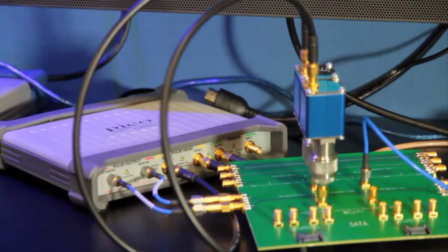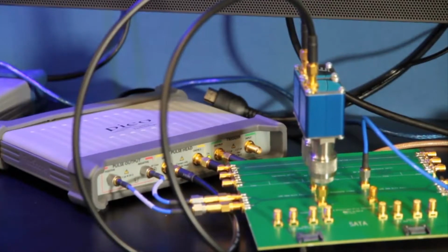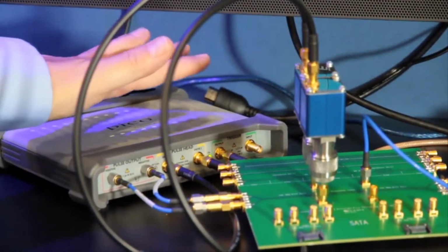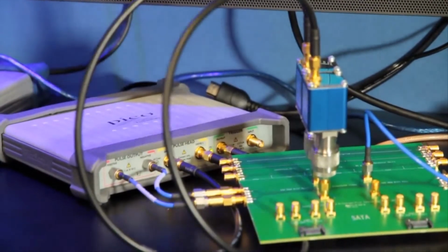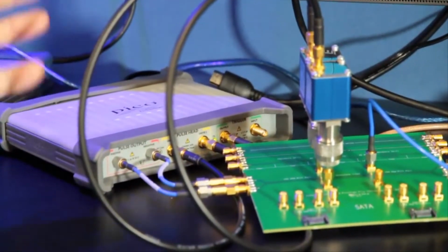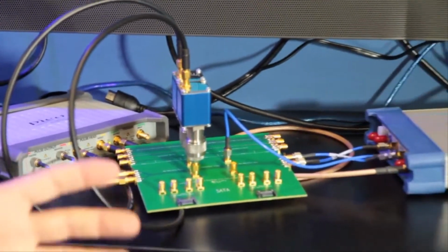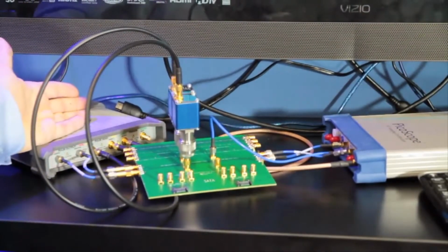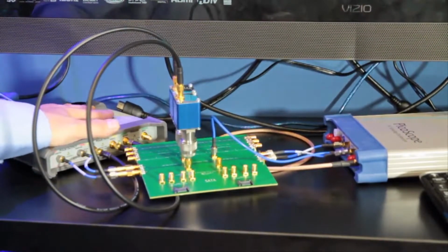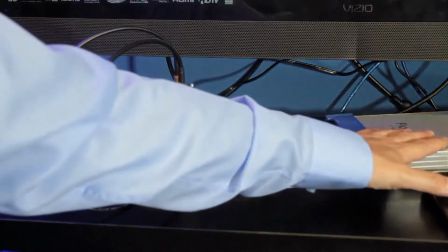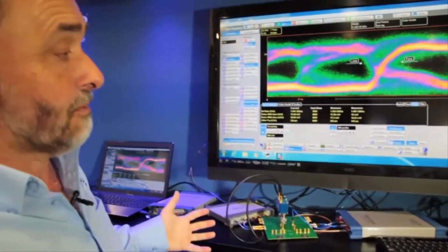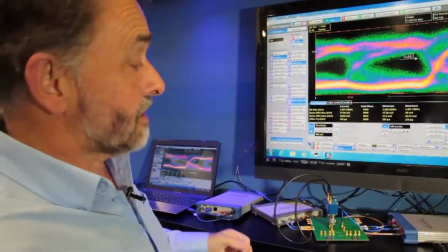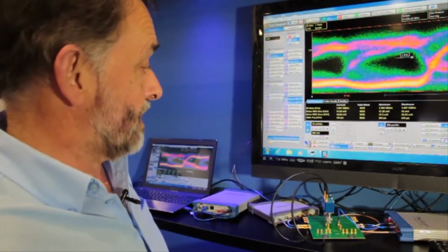Essentially the same technology as we saw previously integrated into the scope, but here we package it separately. We use the 2 products together, and in this case, of course, we have the flexibility to put our time domain transmission source perhaps remotely from our receiving sampling oscilloscope, giving us more flexibility in the product and enabling us to achieve the particular configuration that we need.